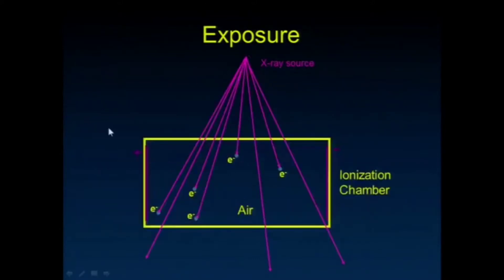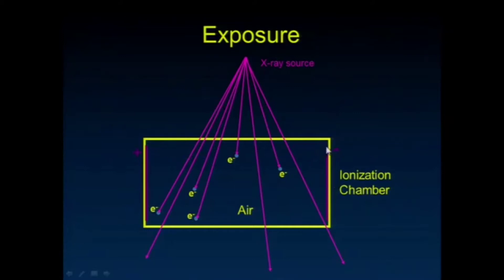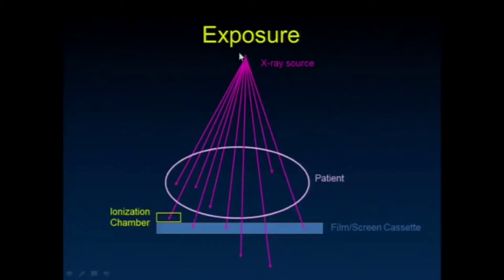You fill a chamber with air, expose it to an x-ray source, and because of interactions where electrons are kicked out of shells, ions are created that flow toward the positively or negatively charged plates — holes versus electrons — and you measure a current flowing through that circuit proportional to the exposure.